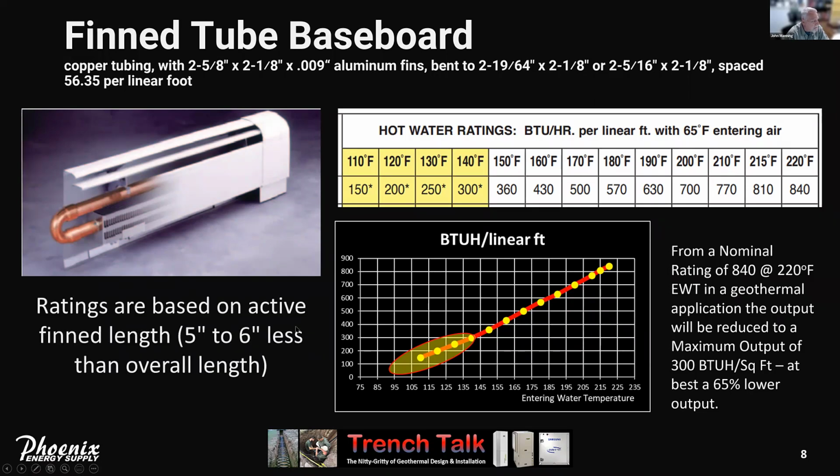The other aspect you have to keep in mind when you go in and size up a house is that these ratings are per foot of actual fin tube area. And quite often with baseboard, the sheet metal is hiding bare tubing, because sometimes they want to go wall to wall in this decorative cabinet and may only have 3 or 4 feet of fin tube hidden behind it. So when you size up a baseboard application, you really have to take the covers off or get a way to see in there to see exactly how much fin tube you have.